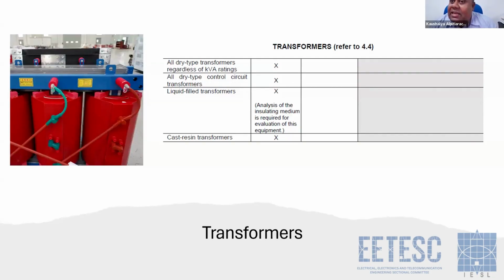Cast resin transformers are said to be replaced, because if you see the cursor, you have these elements where the connection limbs for each winding are connected, the tap changing positions. The core itself is fully enclosed with a resin. But these are the areas where you have a poor IP rating. If submerged at these locations, water can definitely ingress. And this particular winding is a sealed one, so you can't rehabilitate. And the core is open.